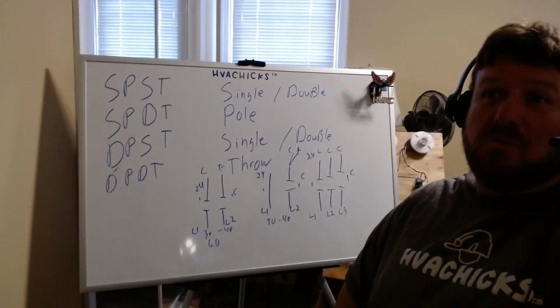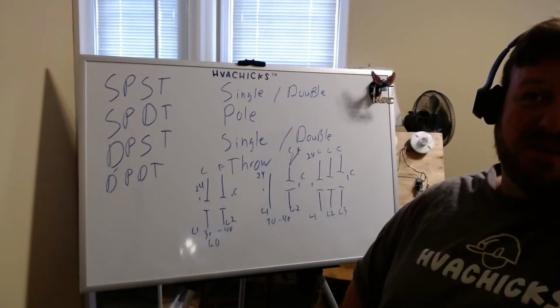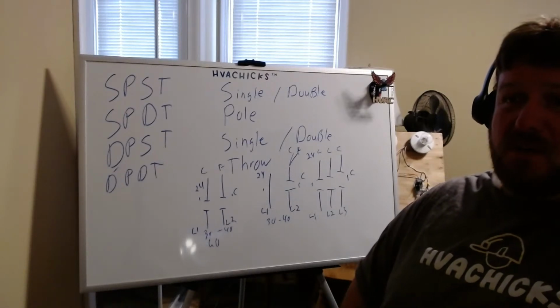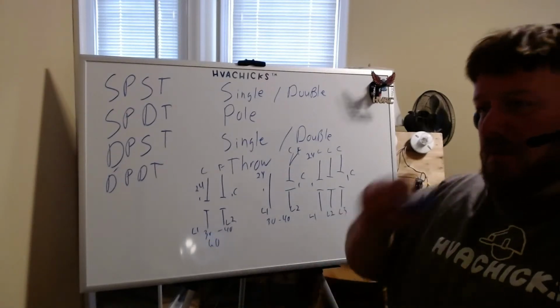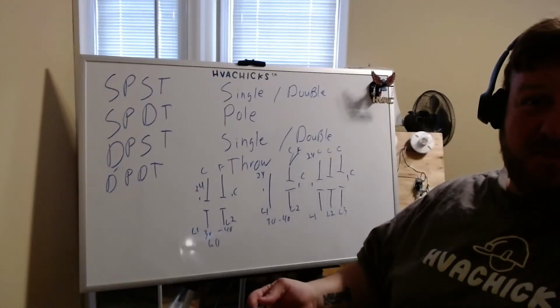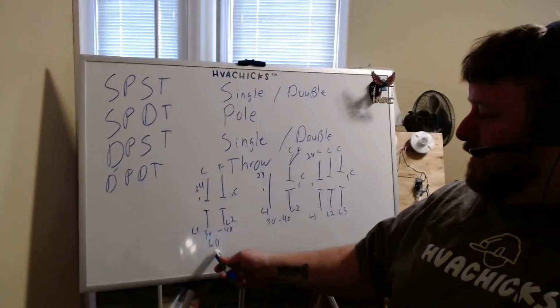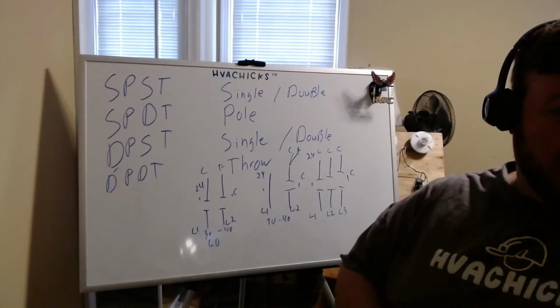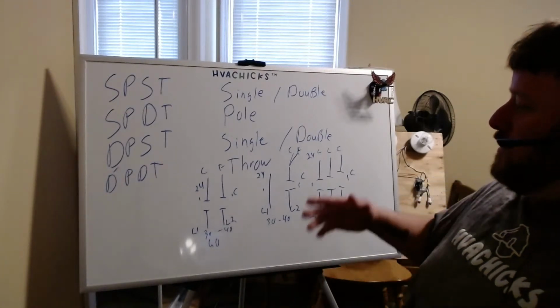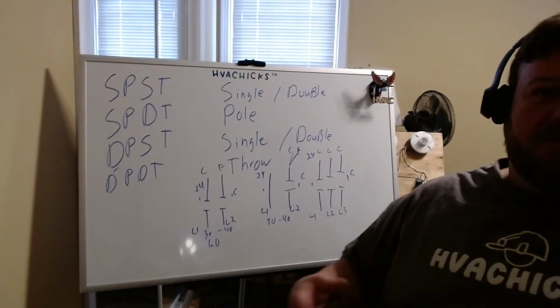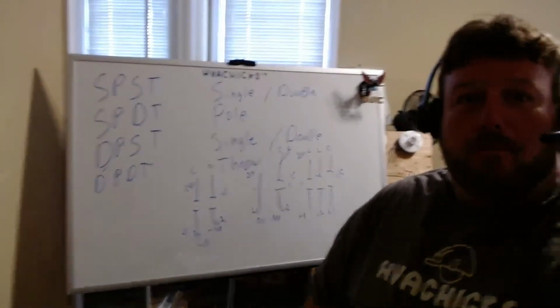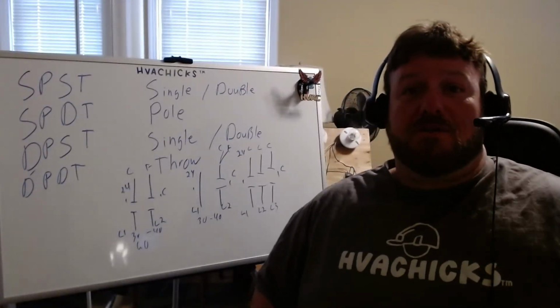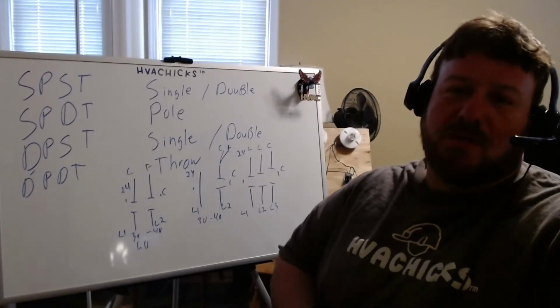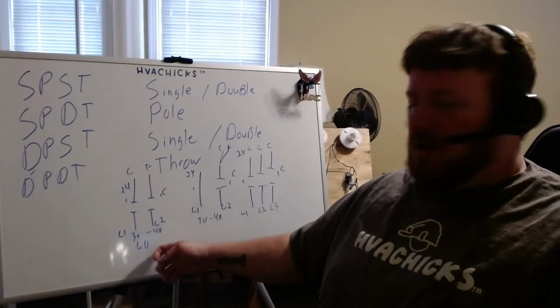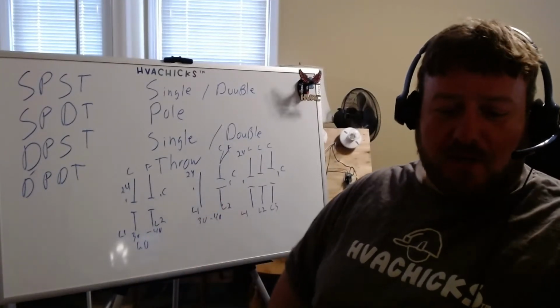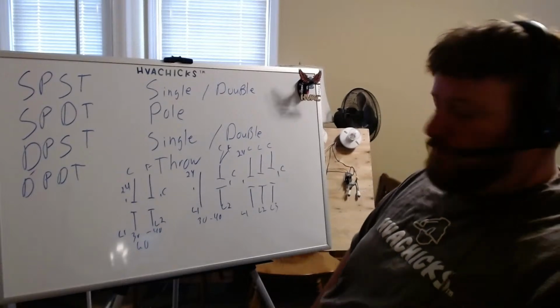So a double pole for a 2.5 ton unit that only does say 40 amps, where a 5 ton requires a 60 amp fuse because it can pull more amperage, might require a 60 amp contactor, double pole. You just got to look at those numbers and read and make sure you do that. Now, everyone out there in the industry, we all stock parts, just numerous. And we try to stock the higher of the two. That way you make sure that you're always covered on everything you do.